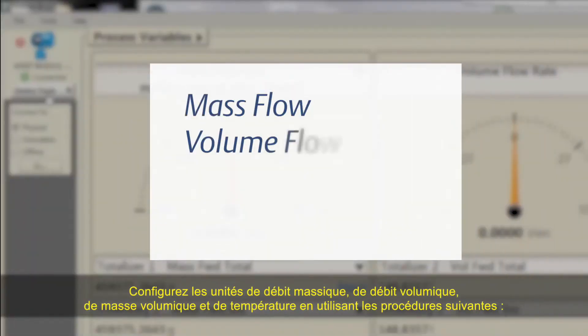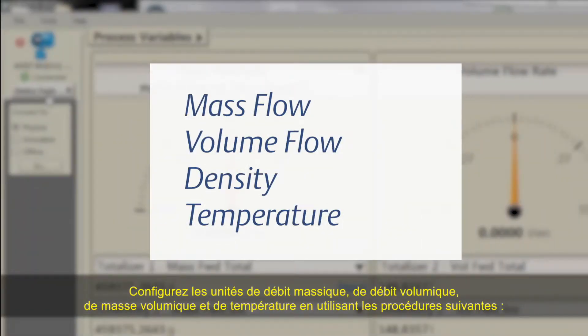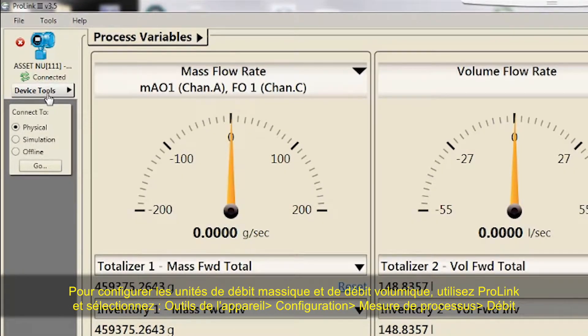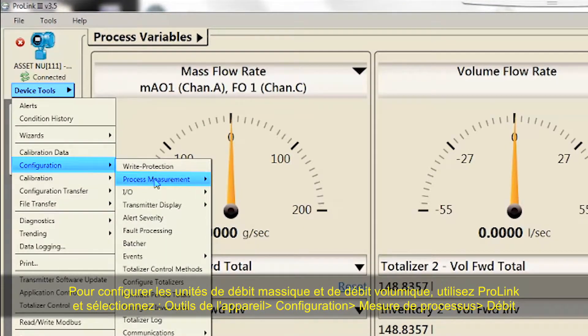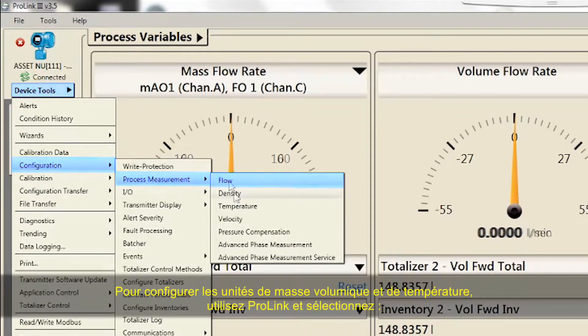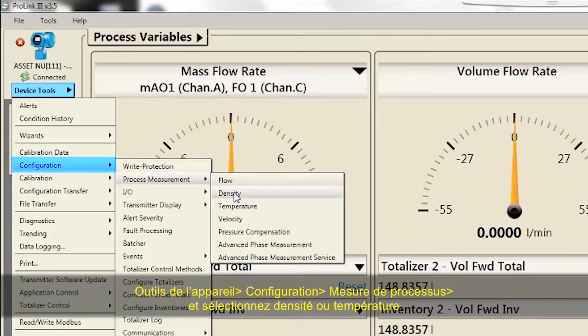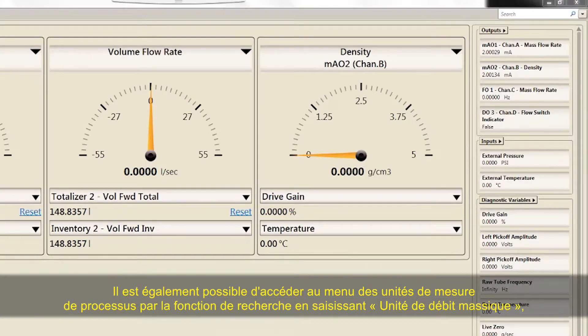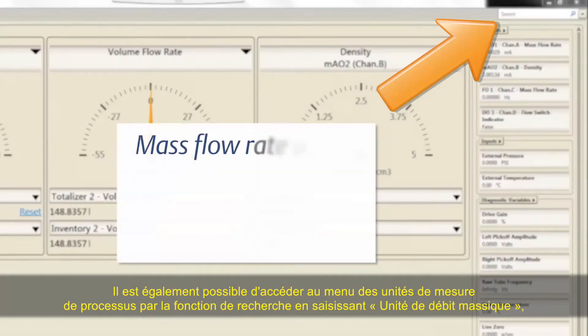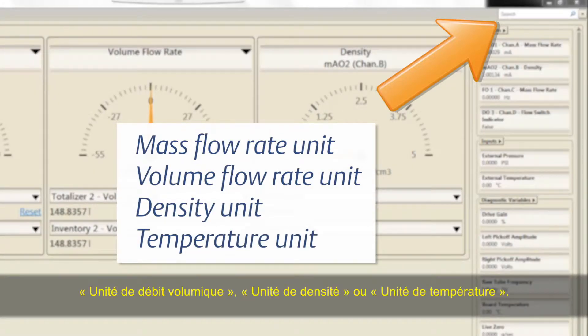Configure the units for mass flow, volume flow, density, and temperature using the following procedures. For configuring mass and volume flow units, use ProLink and select Device Tools > Configuration > Process Measurement > Flow. For configuring density and temperature units, select Device Tools > Configuration > Process Measurement and select Density or Temperature. These menus can also be accessed via the search function by typing Mass Flow Rate Unit, Volume Flow Rate Unit, Density Unit, or Temperature Unit.